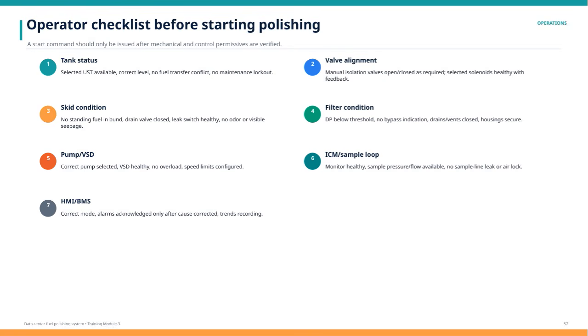For the ICM and sample loop, verify the monitor's health, ensure sample pressure and flow are available, and check for any leaks or airlocks in the sample line. Lastly, review the HMI and BMS settings. The system should be in the correct mode. Alarm conditions should be acknowledged only after their causes have been addressed, and trends must be actively recording.